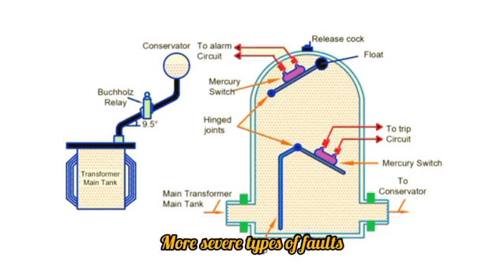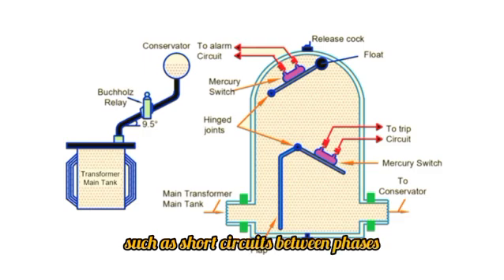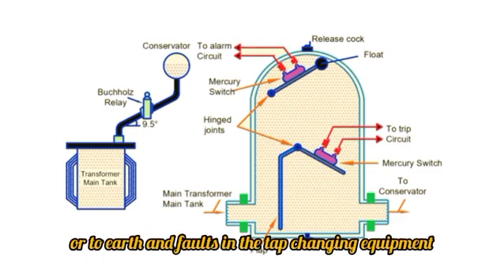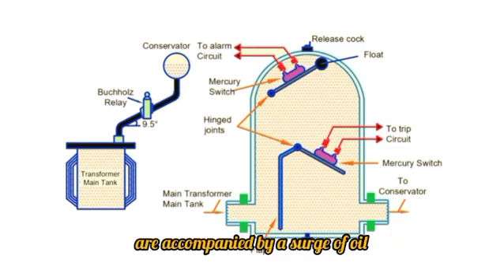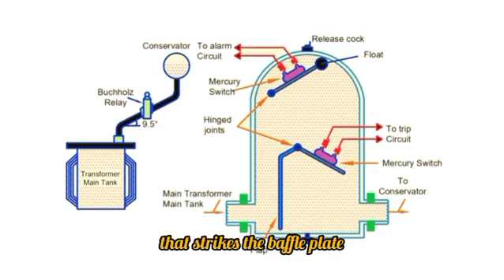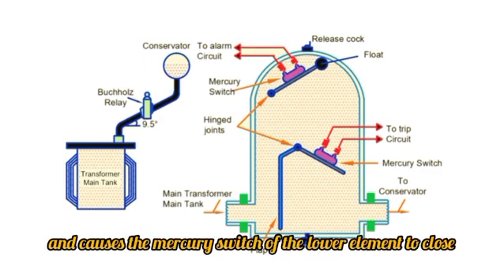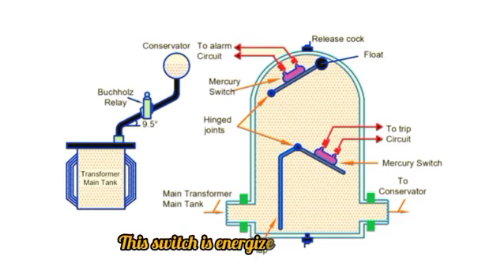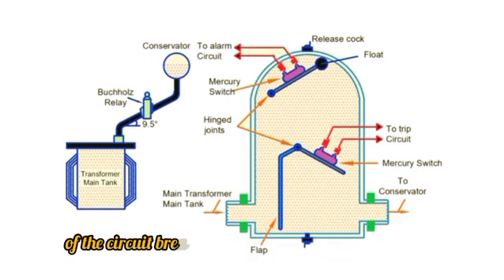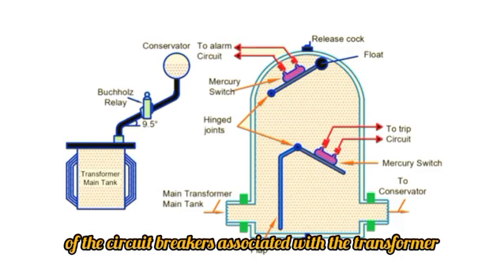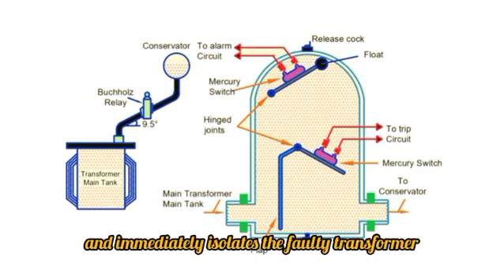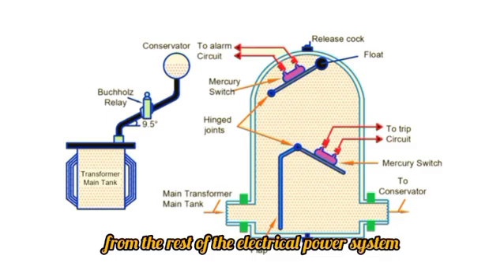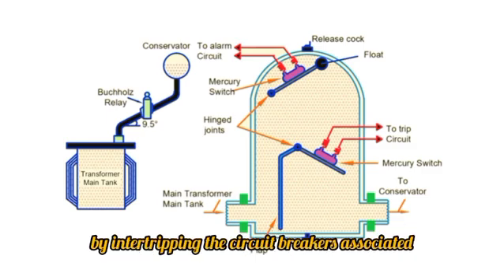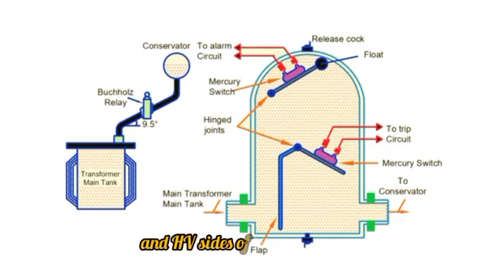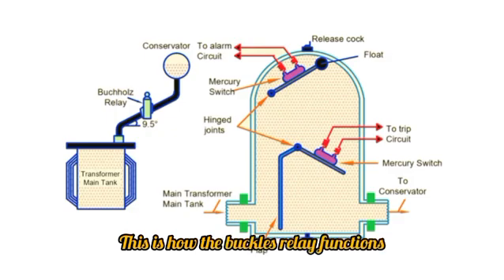More severe types of faults, such as short circuits between phases or to earth and faults in the tap changing equipment, are accompanied by a surge of oil that strikes the baffle plate and causes the mercury switch of the lower element to close. This switch energizes the trip circuit of the circuit breakers associated with the transformer and immediately isolates the faulty transformer from the rest of the electrical power system by intertripping the circuit breakers associated with both the LV and HV sides of the transformer. This is how the Buchholz relay functions.